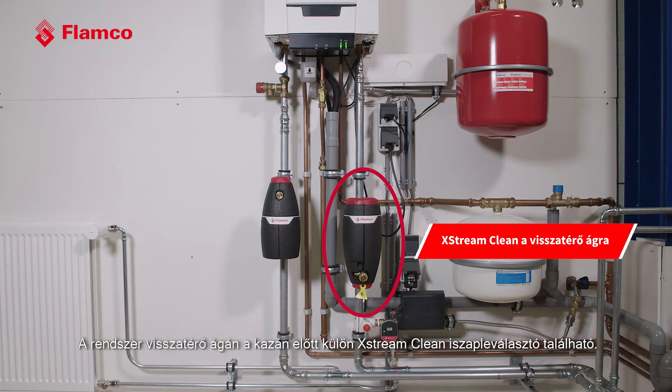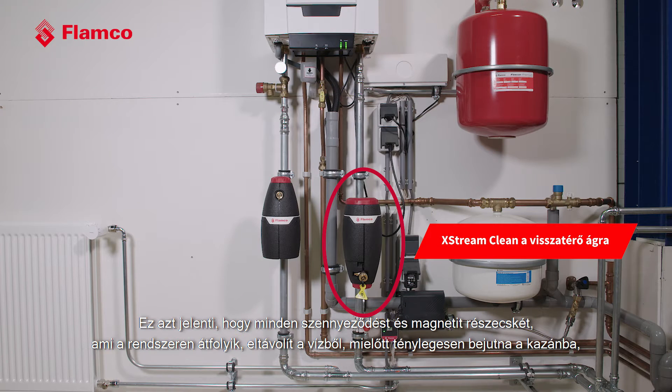We have a separate XStream Clean on the inlet to the boiler, and what that does is guarantee that we take any debris or particles flowing through the system and remove them from the water before it gets into the boiler and potentially clogs the heat exchanger.